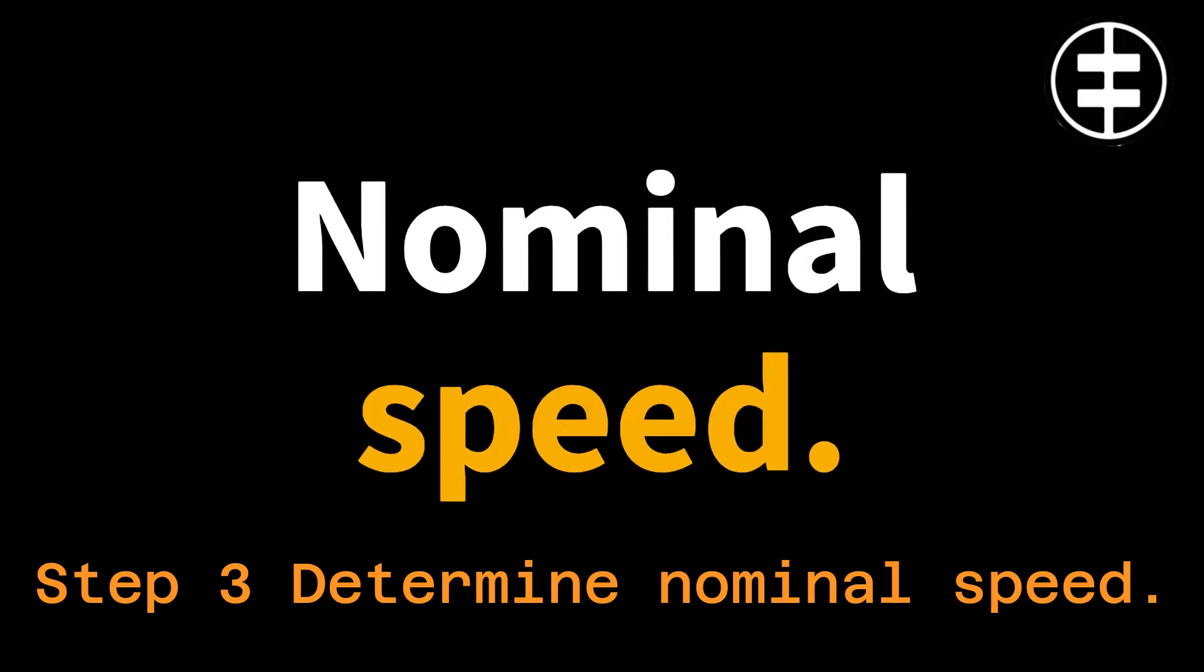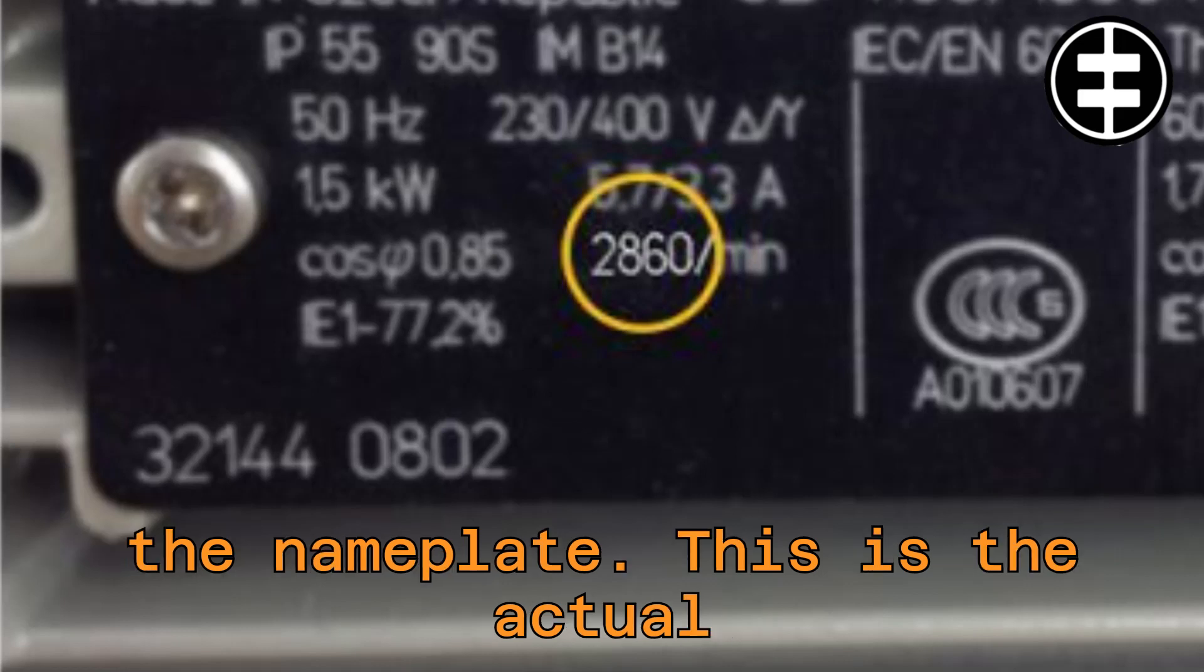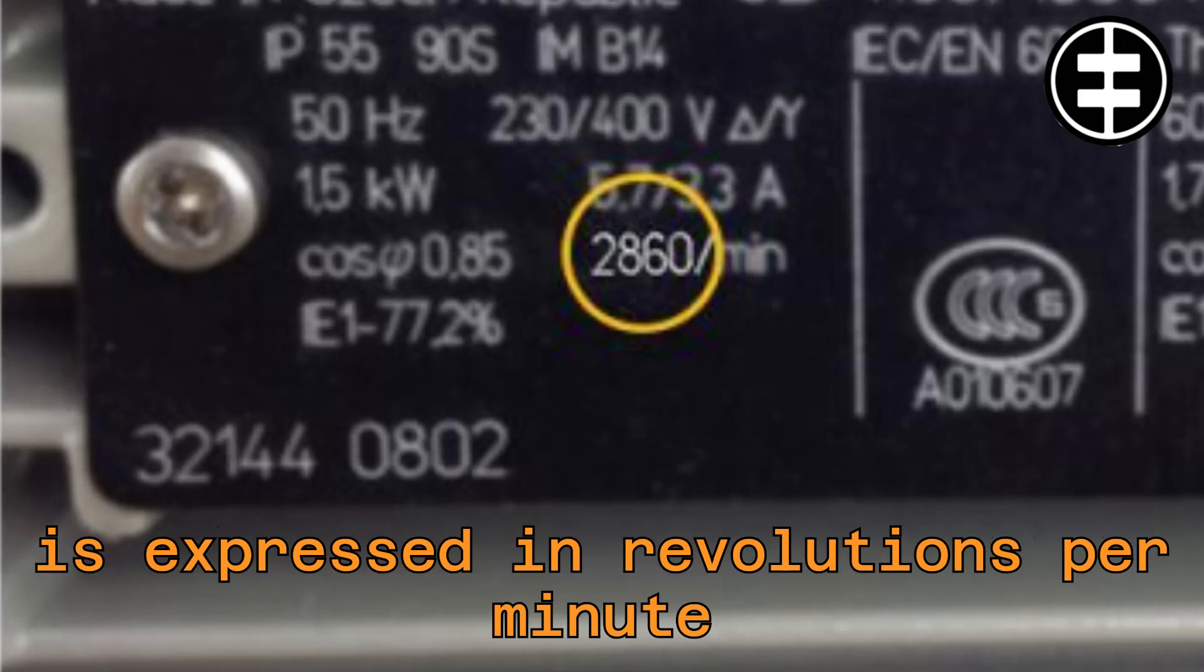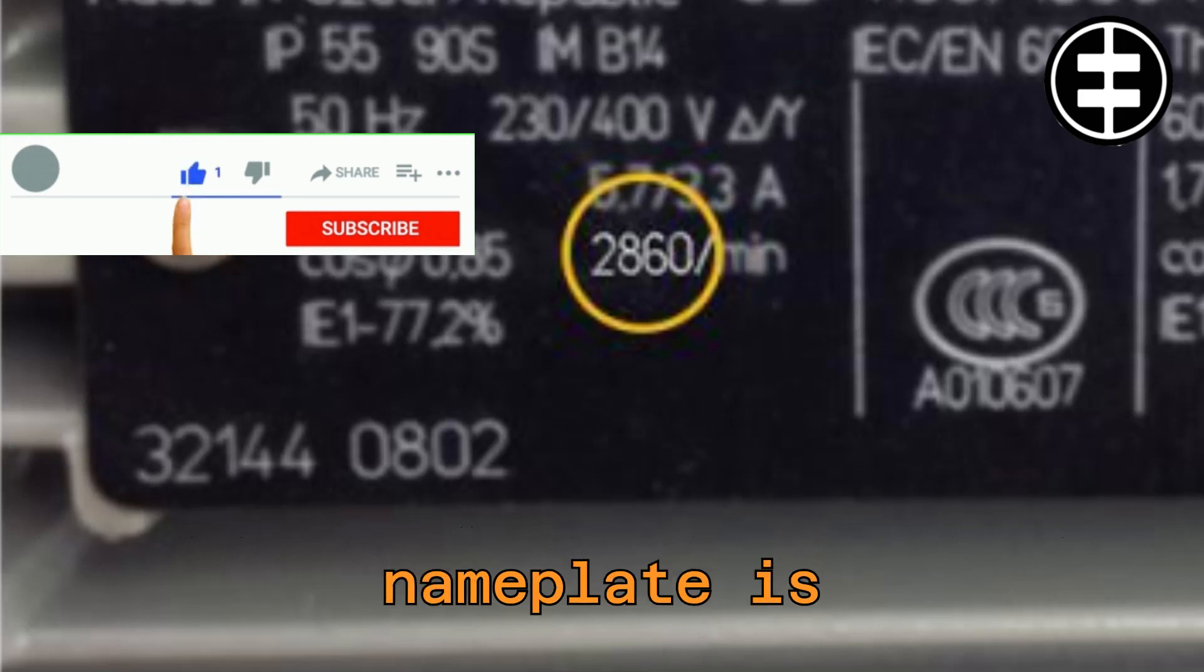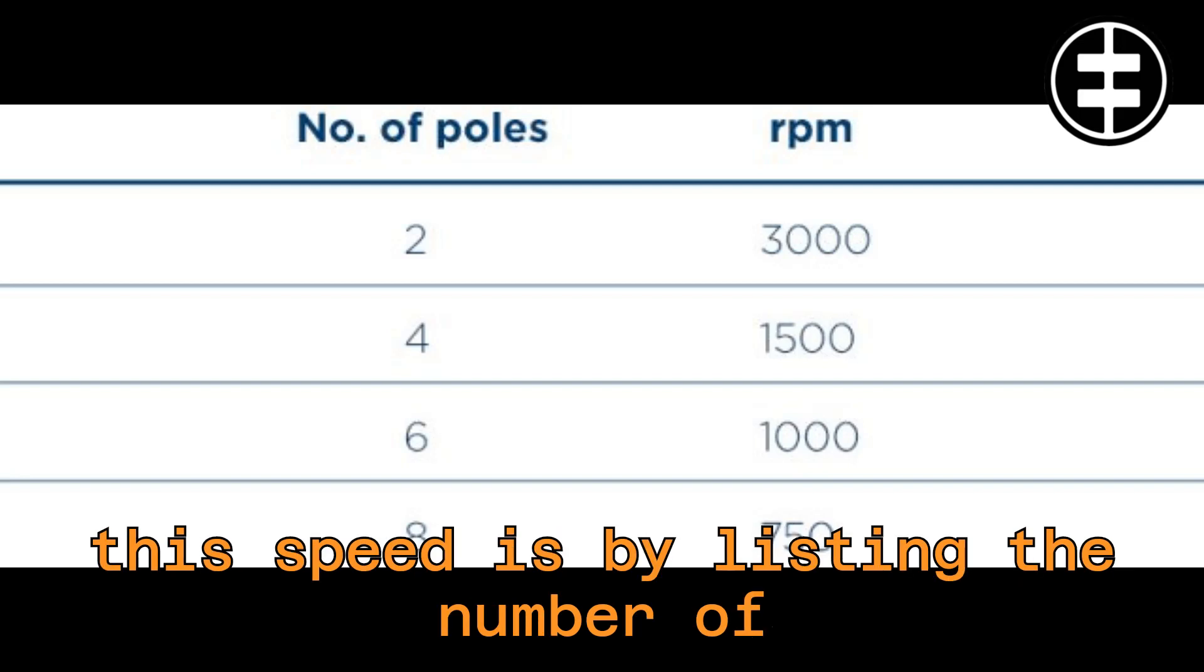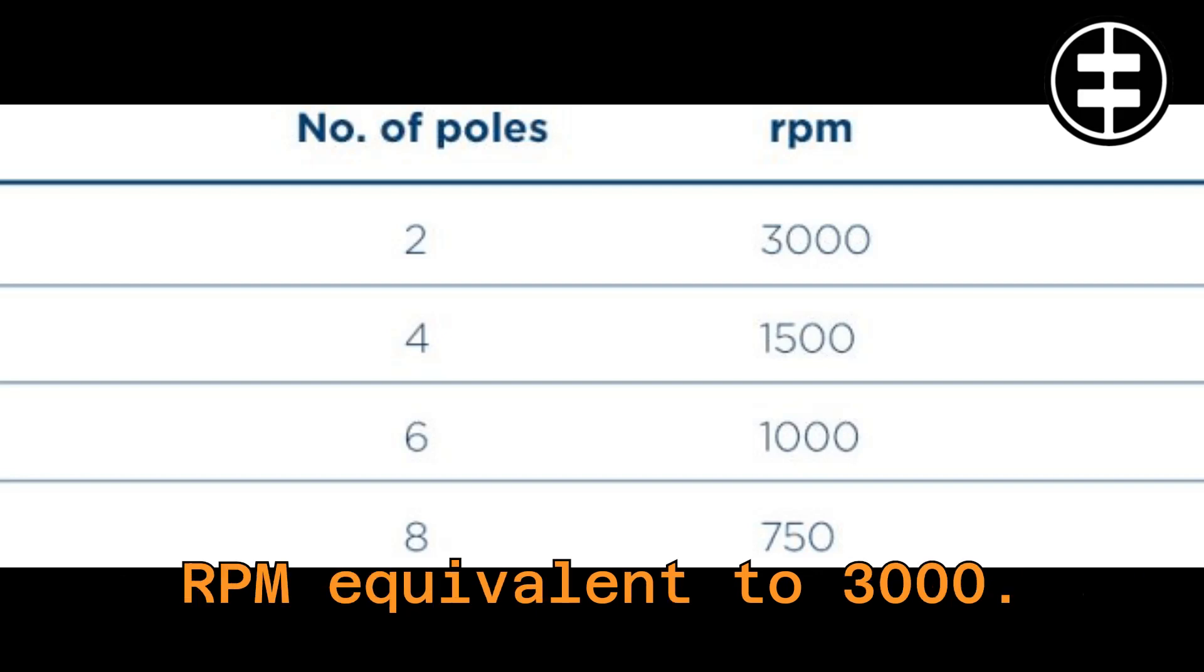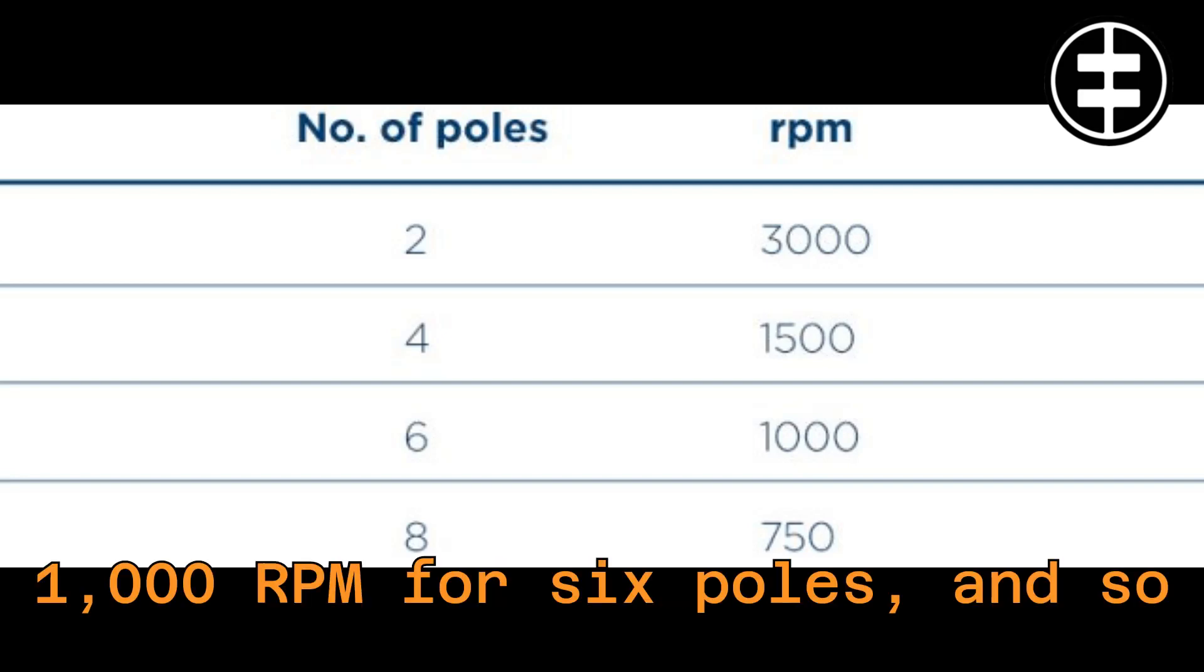Determine nominal speed. The nominal speed is usually stated on the nameplate. This is the actual rotational speed of the output shaft and is expressed in revolutions per minute, or RPM. The RPM on our nameplate is 2,860 revolutions per minute. An alternative way of expressing this speed is by listing the number of poles. A two-pole motor has an RPM equivalent to 3,000. For four poles, this is 1,500 RPM, 1,000 RPM for six poles, and so on.